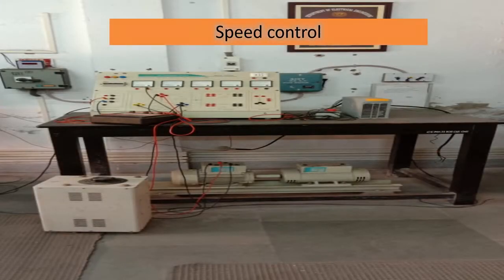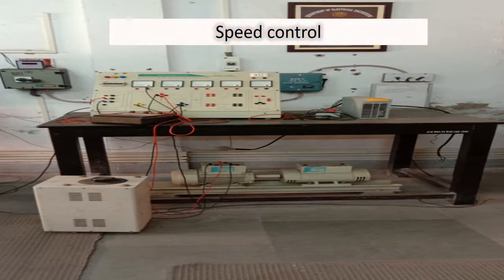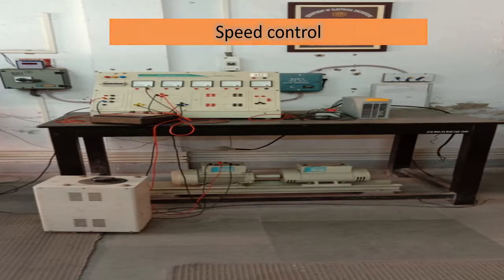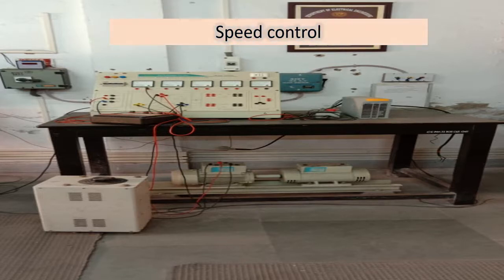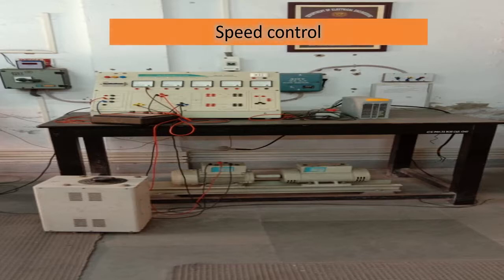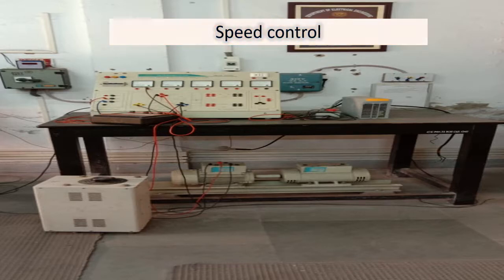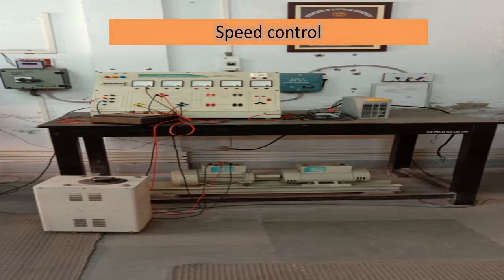This is the experiment on speed control of a 3-phase squirrel cage induction motor by different methods and their comparison. The objective is experimental study of starting and running features with different starting methods for a 3-phase squirrel cage induction motor. Two types of control are there. One is stator voltage control. Developed torque in case of an induction motor is proportional to the square of terminal voltage at a constant value of supply, and the other is variable voltage frequency control. By changing the supply frequency, the speed of the motor can be controlled.